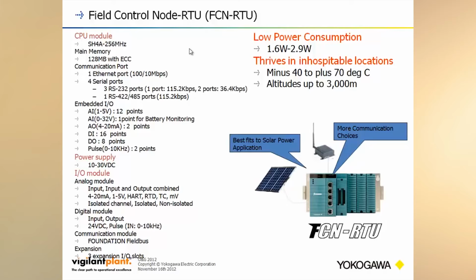It has low power consumption and is good in various different environments. It has a good chunk of embedded I/O as well. It's got 12 points of analog, 1 point for battery monitoring, and a couple of analog outputs, which is good for things like PID loop control. It's got 16 digital input points, 8 digital output points, and a couple of high-speed pulse points for doing PD meters and other types of flow meters that could generate pulses for you.